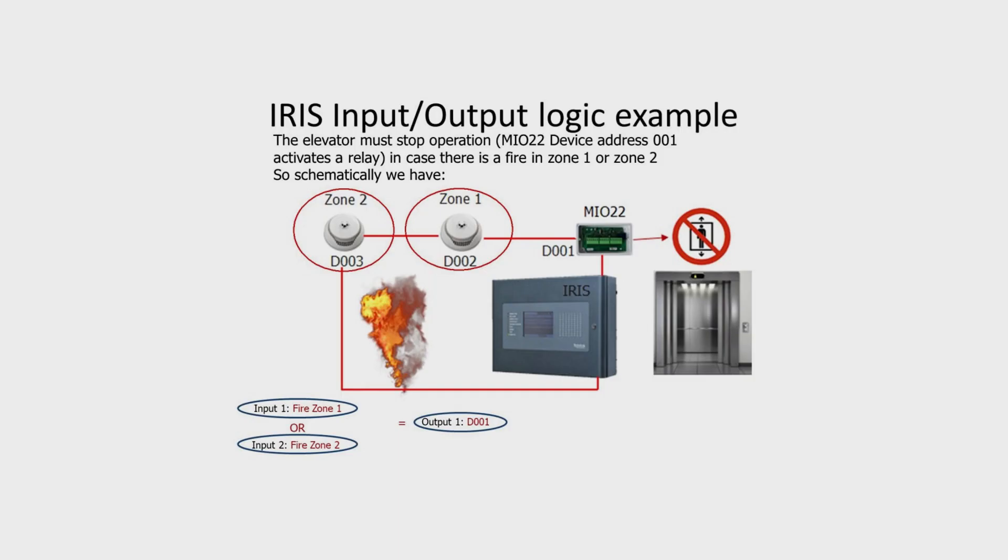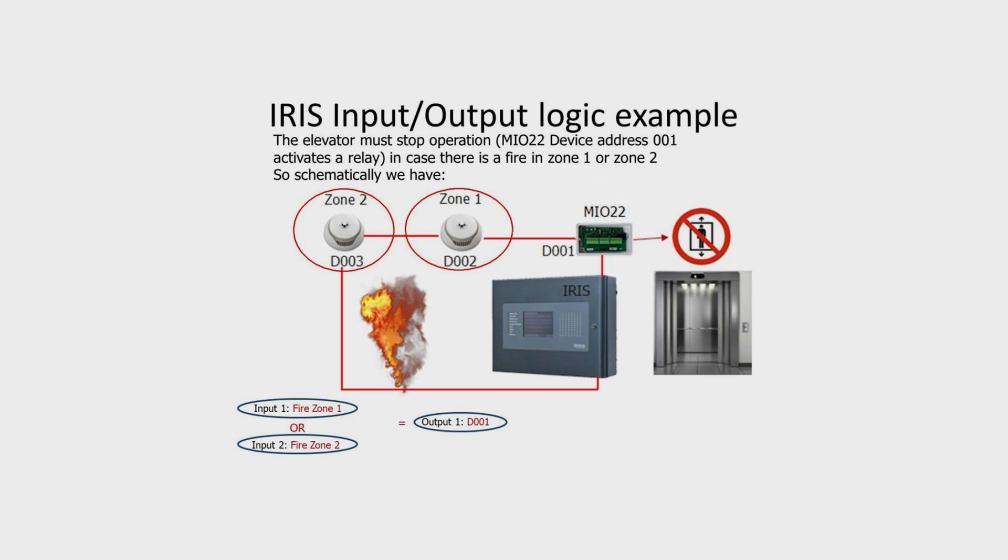In this input-output logic example the elevator must stop operation in case of a fire in zone 1 or zone 2. We are using a relay output of the Mio module that is going to stop the elevator. We have two detectors, one of them is in zone 1 and the other in zone 2.